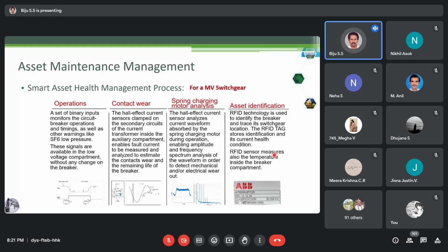This is a smart health monitor for an MV switchgear, with a set of binary inputs. In every IED, there are binary inputs and binary outputs. The binary input will monitor circuit breaker operations and timings, as well as other warnings like SF6 low pressure. These signals will be available in the low voltage compartment, and the contact wear indication shall be obtained. Every breaker will have a fixed and moving contact, and if the contact gets worn out, the breaker will fail.